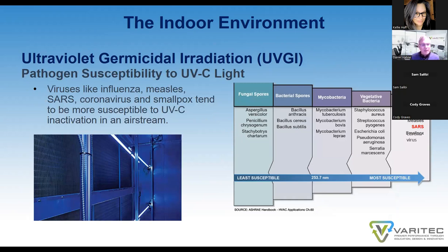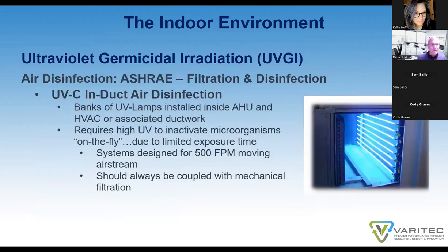These devices can be placed at cooling coils, at the discharge side of a cooling coil normally, though they can also be put upstream of a cooling coil. We like to put them downstream because they can more effectively kill any bio growth that might grow due to the condensing coil in the vicinity of the coil and the drain pans. So it's very effective. Air handlers have to be designed to allow enough air travel within the air handler and exposure of the air to the UV lights for it to be effective. And that would be coordinated with the manufacturers laying out the air handlers and the UV light products.